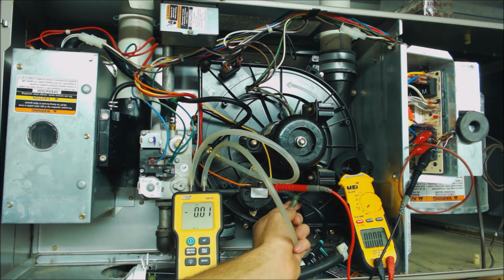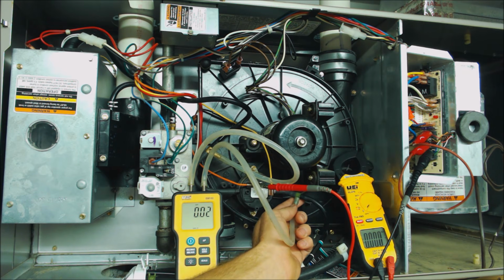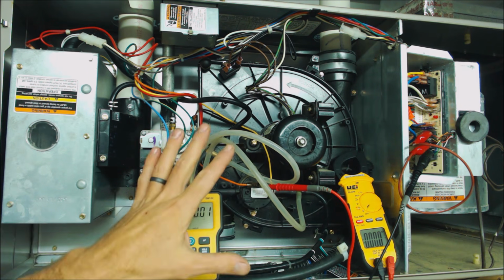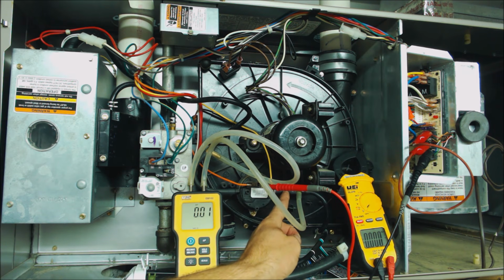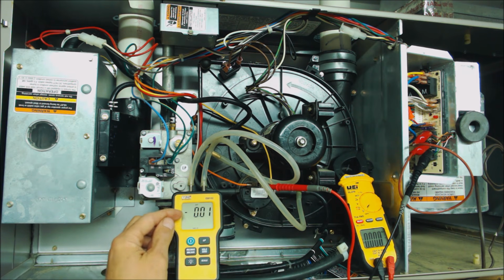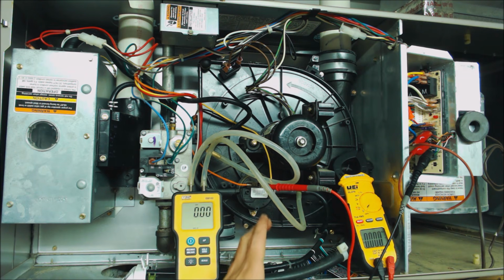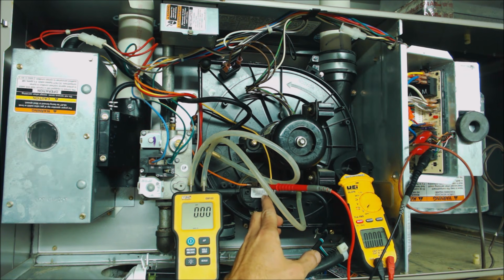You could also use these plastic tees that you get when you change out a furnace. You can just take them out of there. So anyway, that's teed in, and we're going to read our differential across here, and this side should be in a deeper vacuum, so our differential reading should be in negative. Now, if this differential was actually correct, and this model number right here, I looked it up, and it should have a 1.81 negative water column reading. So we would need something higher than that in order for this switch to click.